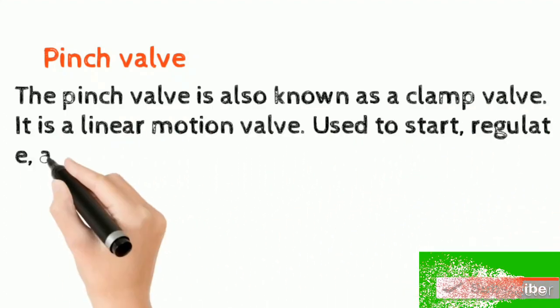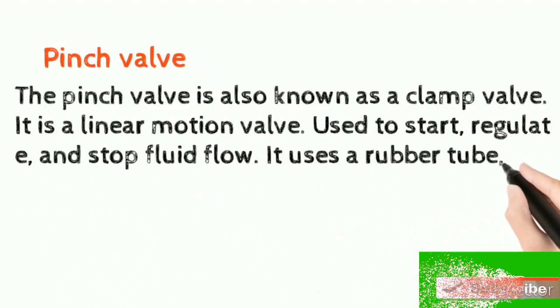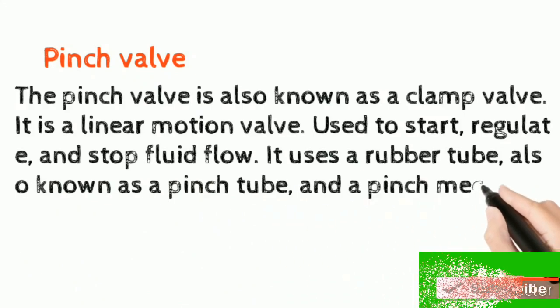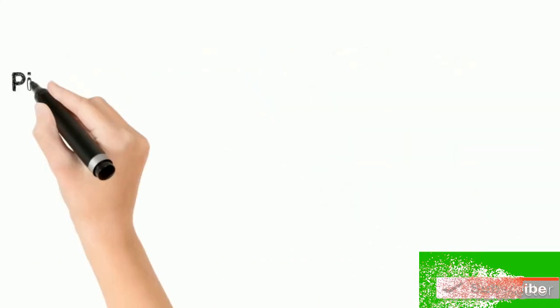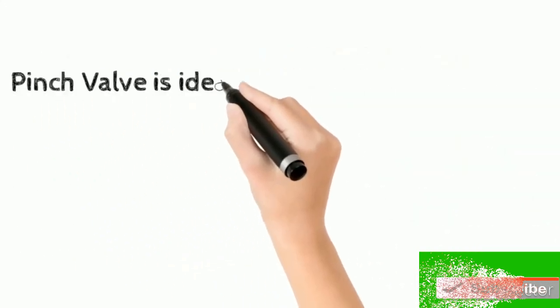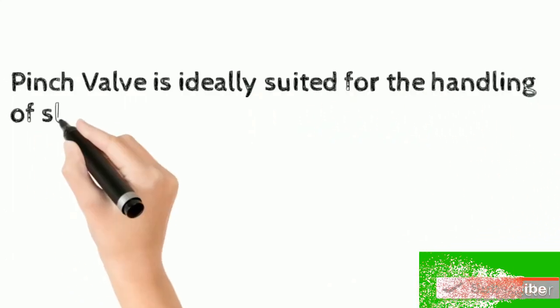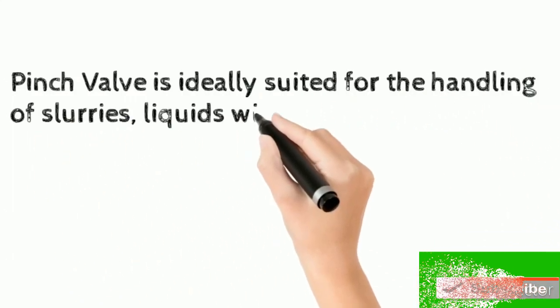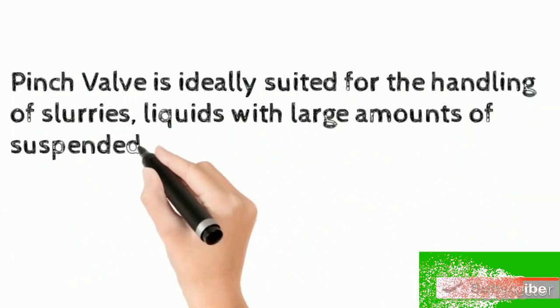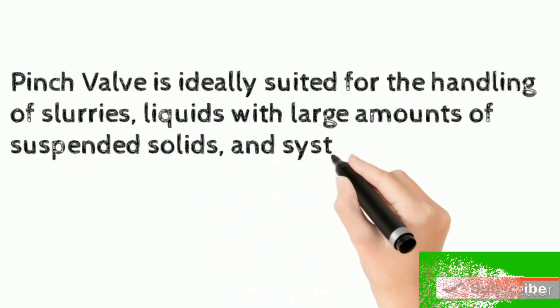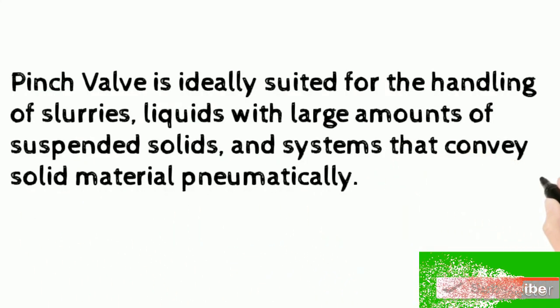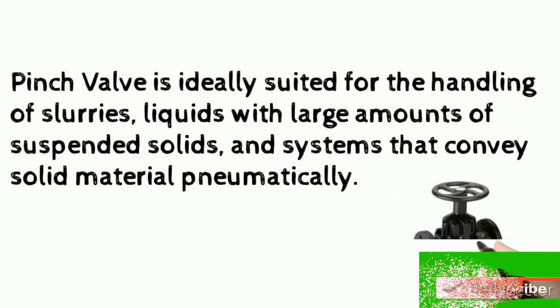The pinch valve is also known as a clamp valve. It is a linear motion valve used to start, regulate, and stop fluid flow. It uses a rubber tube, also known as a pinch tube, and a pinch mechanism to control the fluid. Pinch valve is ideally suited for handling slurries, liquids with large amounts of suspended solids, and systems that convey solid material pneumatically.